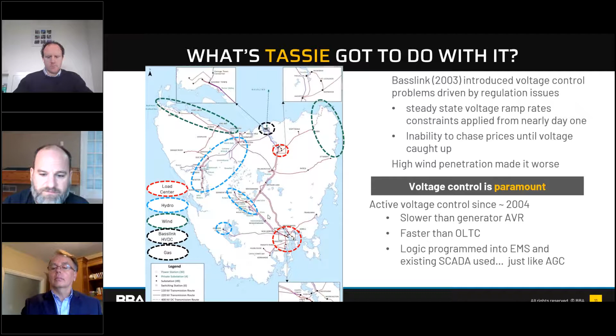So what did they do? From around 2004, I was involved in the first generation of this control, they now have two voltage control schemes. They manage the northern system so they control the voltage at Basslink and Launceston, which is effectively electrically very close, so very much the same voltage point. They control that voltage by regulating the 220 kV to compensate for the regulation characteristic of these lines when they're really heavily loaded.